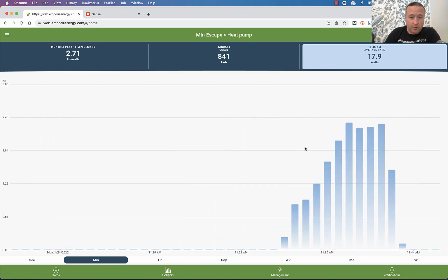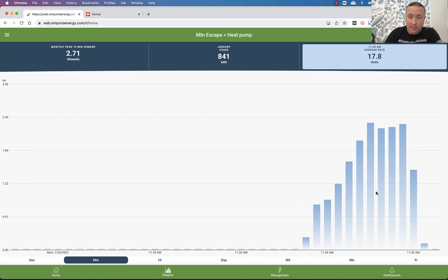And here it is. So these are pretty short pulls. I don't like seeing it run this little, and this is not something I'm happy with in the programming of it. I wish that it would not get so crazy and go up to 2 tons. I wish it would just run up to about a ton and just run.